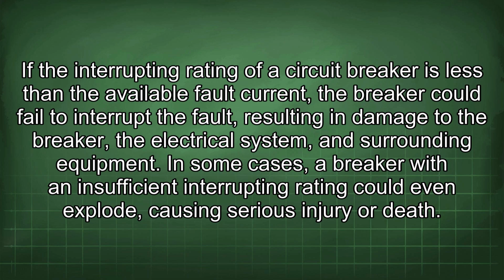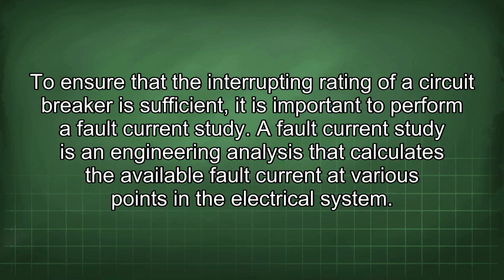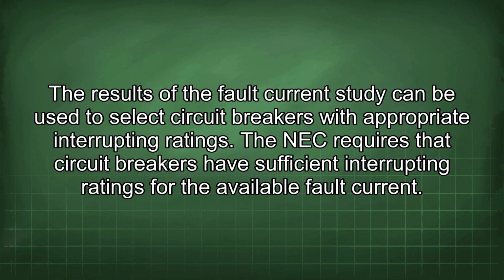In some cases, a breaker with an insufficient interrupting rating could even explode, causing serious injury or death. To ensure that the interrupting rating of a circuit breaker is sufficient, it is important to perform a fault current study. A fault current study is an engineering analysis that calculates the available fault current at various points in the electrical system. The results of the fault current study can be used to select circuit breakers with appropriate interrupting ratings.